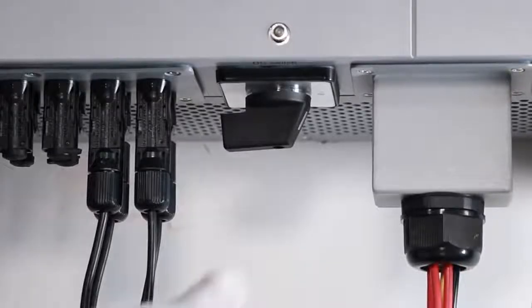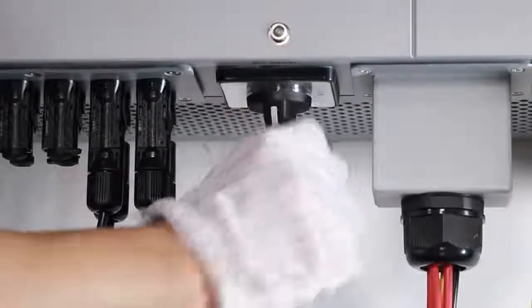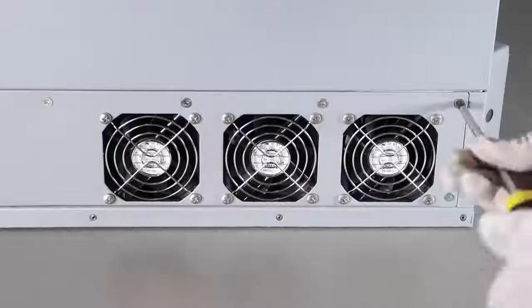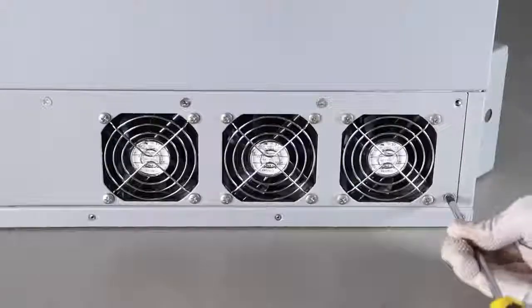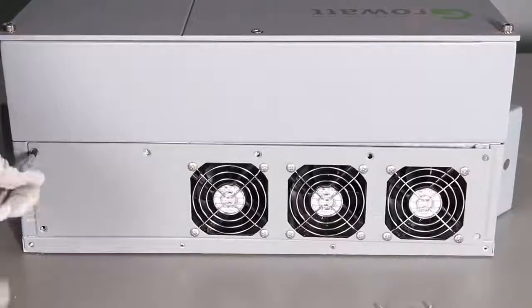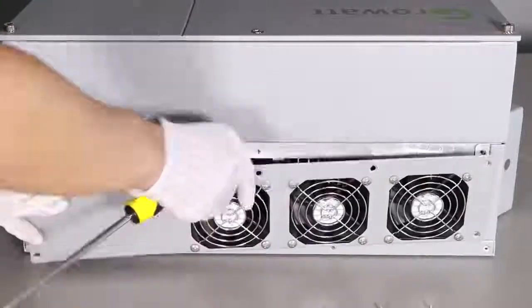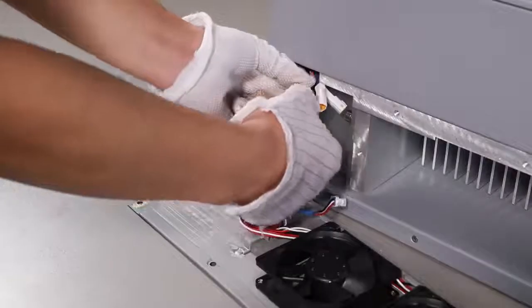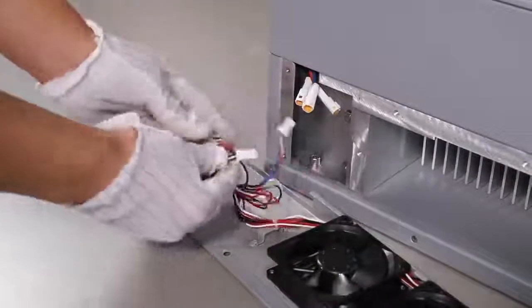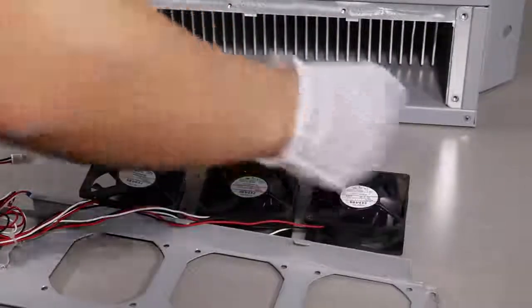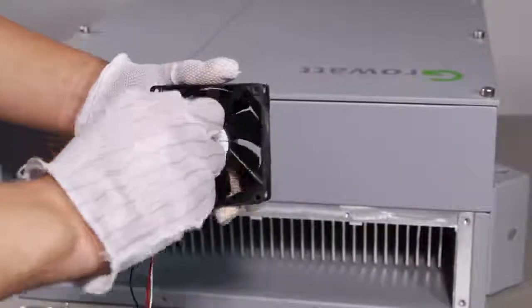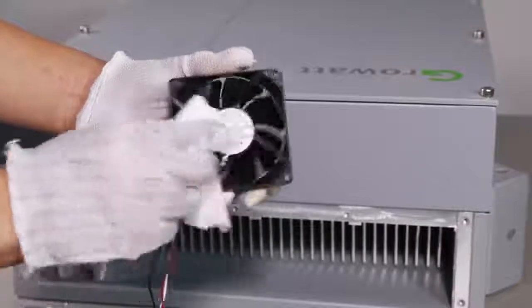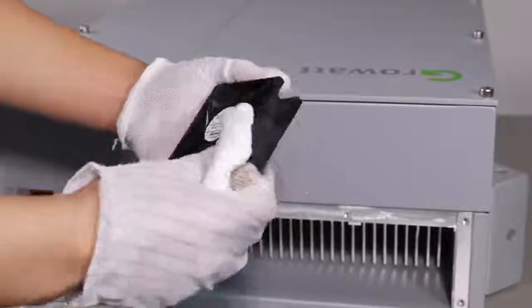Switch off the inverter PV switch, AC switch. Varies for different model. Unscrew the inverter handle and protective part firstly. Unscrew the fan cover screws. Disconnect the fan cables. Take off fans. Use wet towel to clean it. Replace faulty or damaged fans.